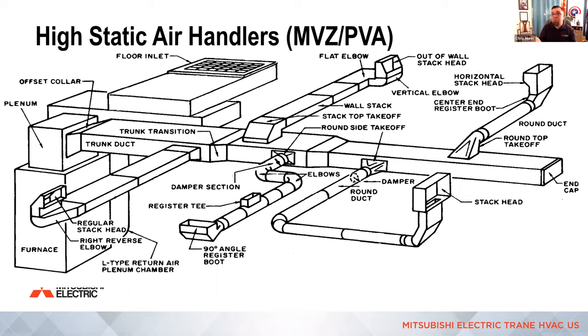This is actually a great picture out of the old Manual D that has every style and name of fitting that is available to residential HVAC contractors. Now, me personally, when I was 16 and I was at a distributor picking up what I had no idea a flat elbow was, it was much easier to order, like when you're ordering food in a foreign country, you can point to the number or know the number. It was much easier for me to get the right part. And that's what a lot of technicians use this for. So that way, when they're making runs or you're designing a system, you know which fitting it's supposed to be. That way, what you design and what is actually installed or picked up is the same fitting, right?